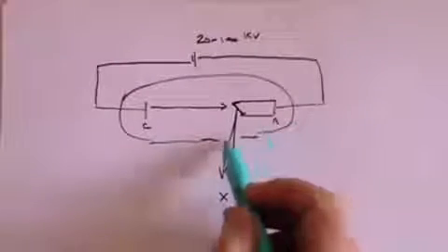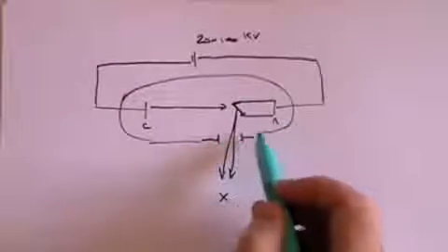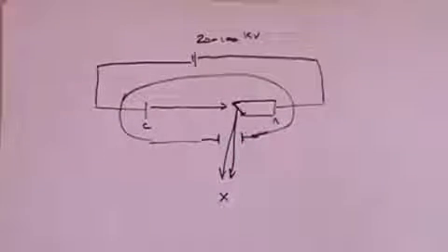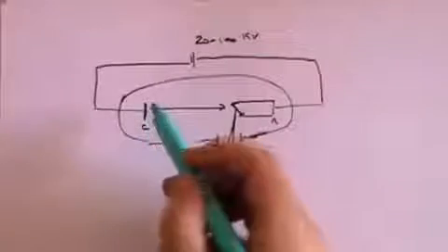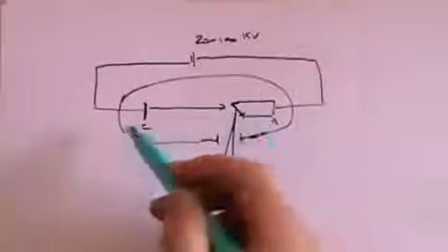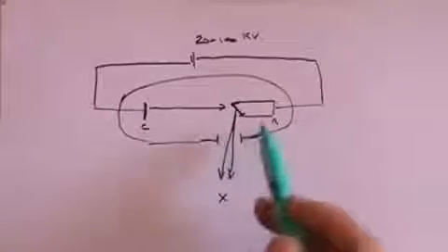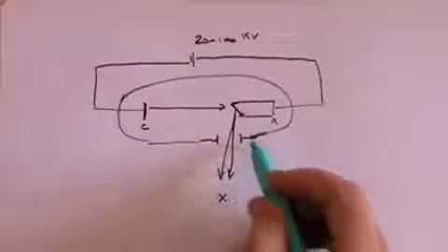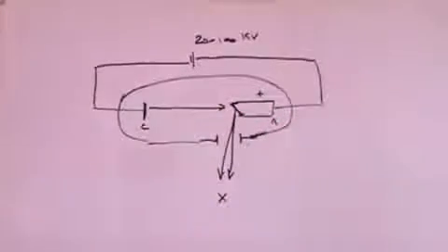And that's why I left the gap there. There's a little window here through which the X-rays pass. The cathode will typically have a separate circuit which heats the cathode in order to drive the electrons out of the cathode, and they are then attracted of course to the positively charged anode.